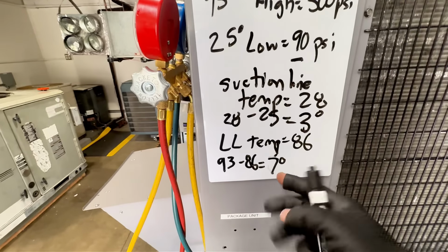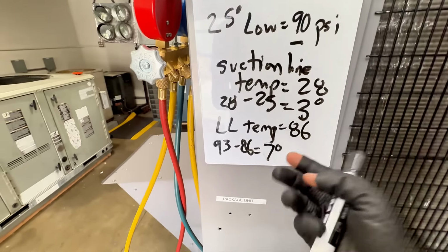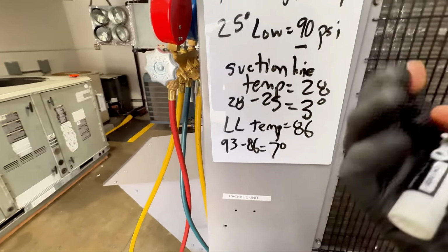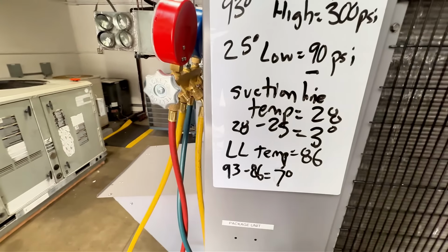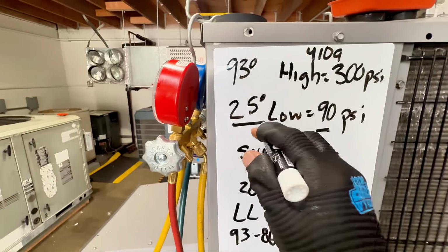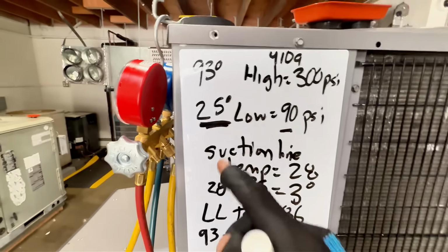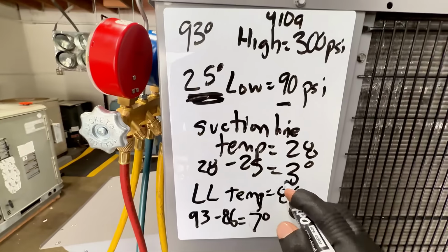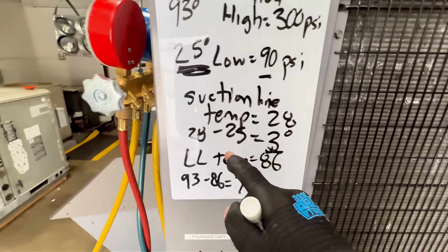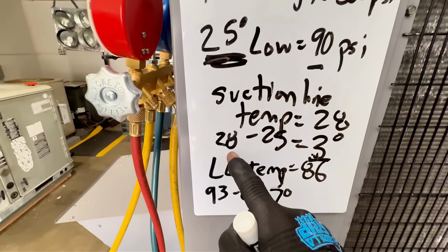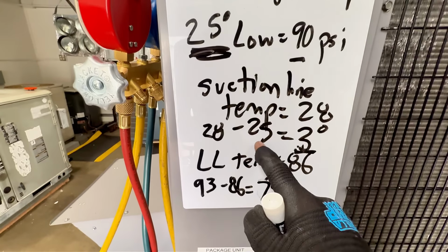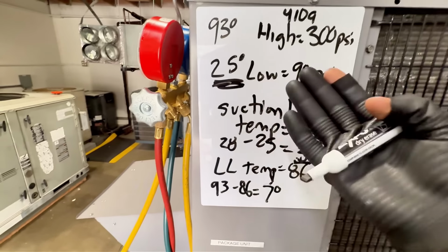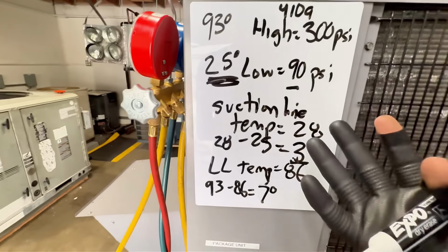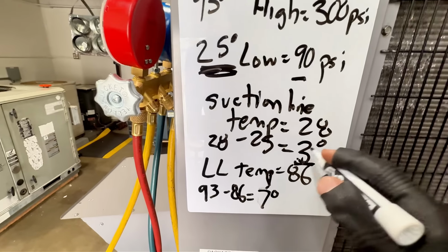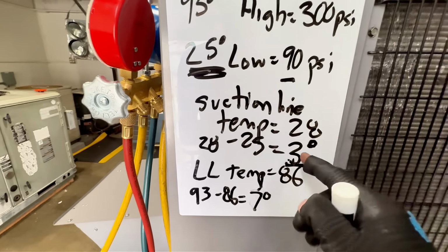You might think, well, it's properly charged because I do have some subcool number. I do have 7 degrees, so I do have some liquid. But right away, I know we have an issue because of this. My evaporator temperature is really low, and my superheat is low. So remember, if the suction line temperature was the same as the evaporator temperature, then you would have liquid going to your compressor. It's still saturated. So we are boiling off some refrigerant because we have a 3-degree superheat.